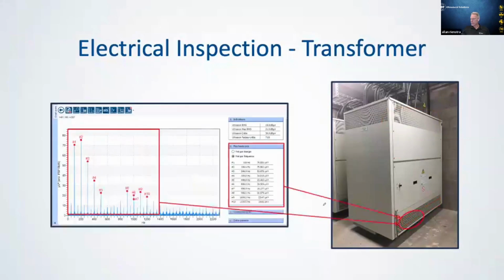And if we look at the signal that we picked up coming from this part of the cabinet here, we're looking at the frequency spectrum, and we can see that these events are all lining up as 50 hertz. So we know that this is not in North America. This is somewhere else where the line frequency is 50 hertz.